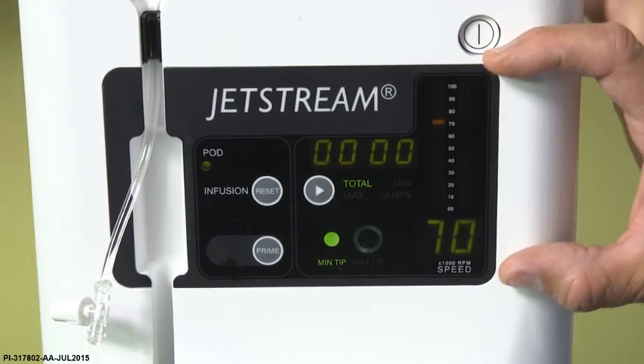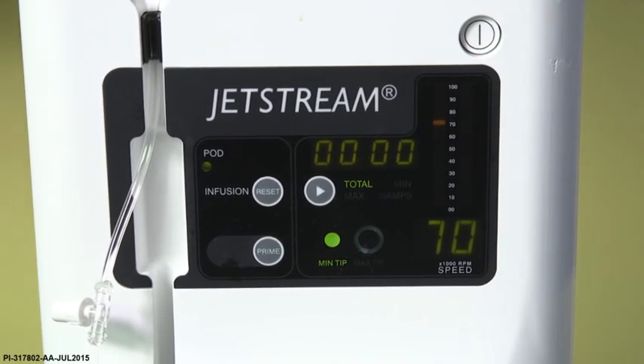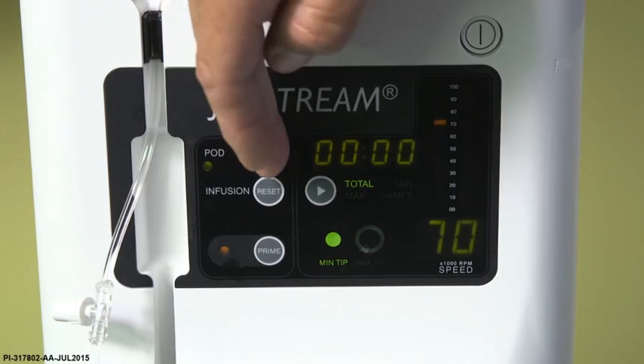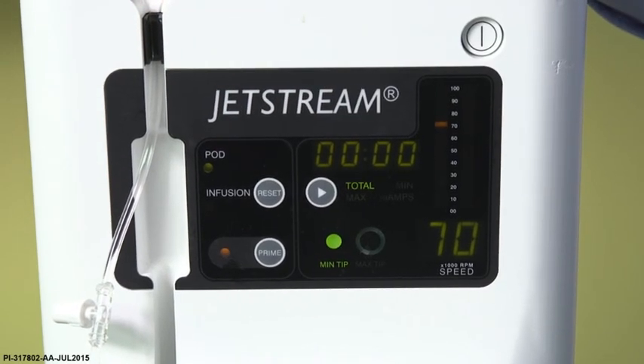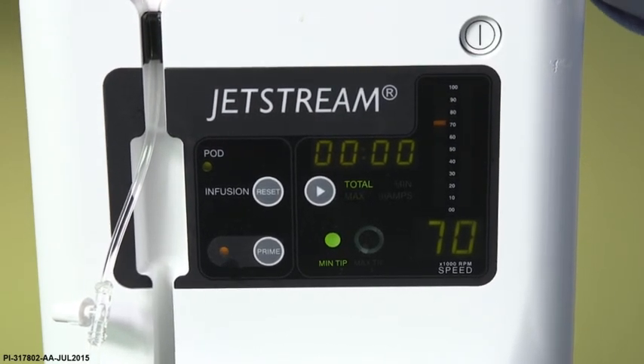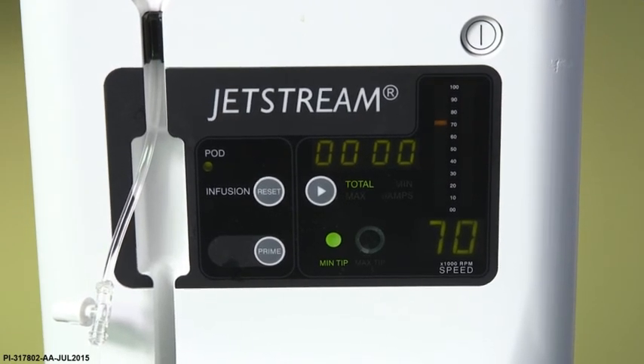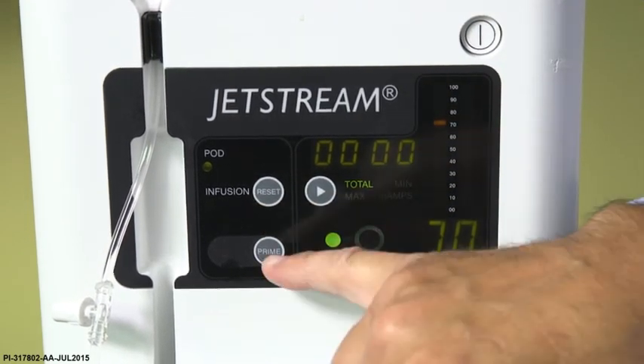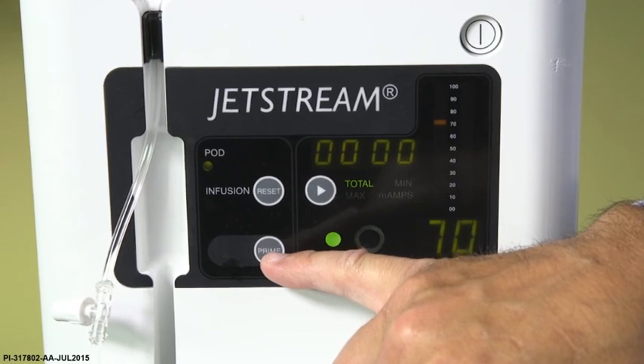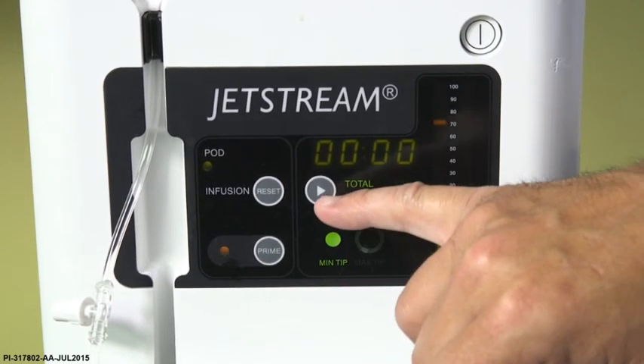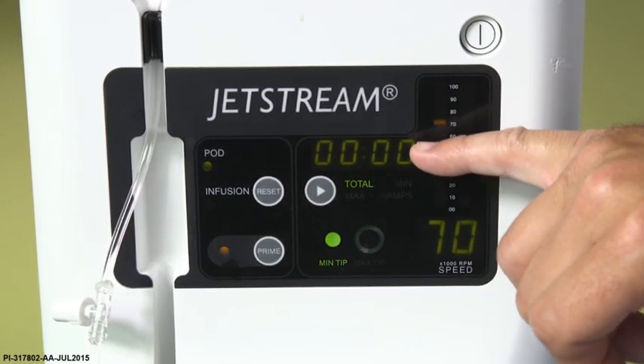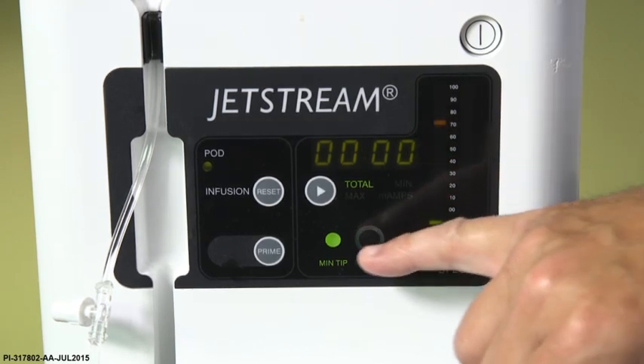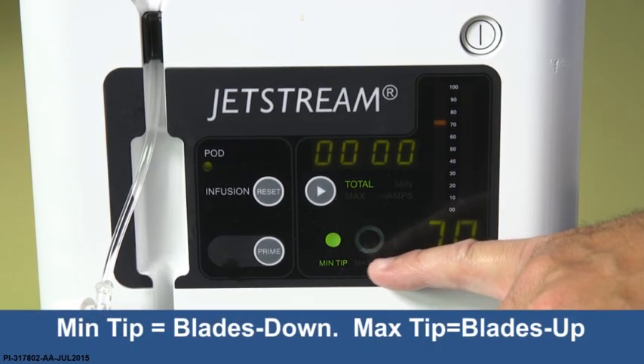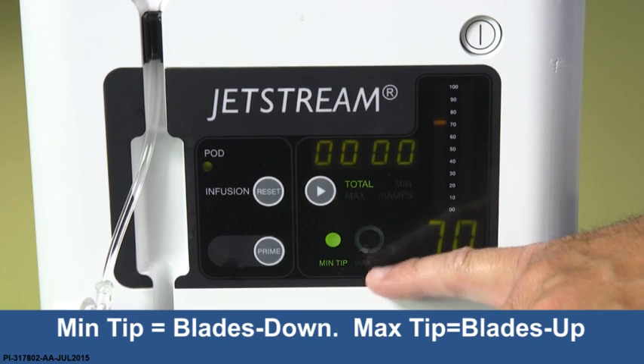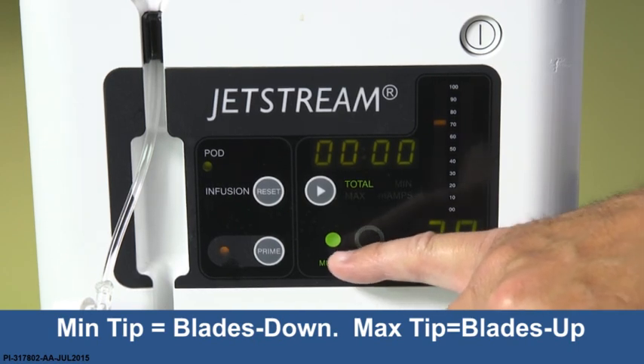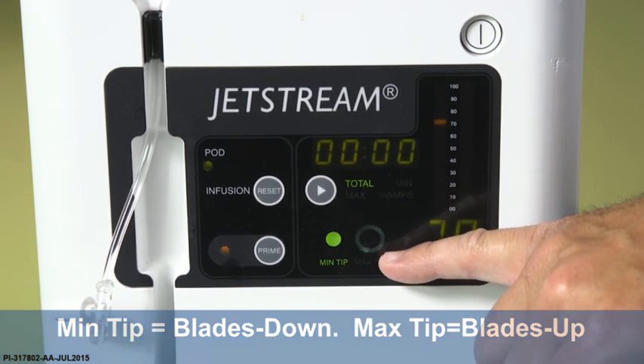A review of the screen real quick on the Jetstream unit. We have several different buttons. The first is a reset button, so if you should encounter any alarms on the system, you will correct the alarm and then hit the reset button. The prime button is used when we prime the catheter. We also have a total runtime here, which indicates the total runtime for the device. And below here we have two indicators indicating min tip and max tip. At any time you can look at the screen and determine which cutting mode you're in.